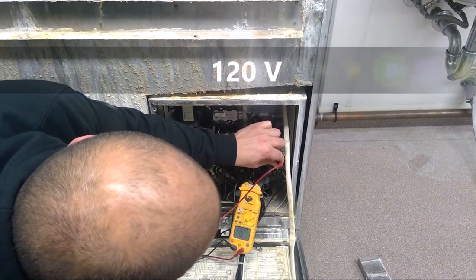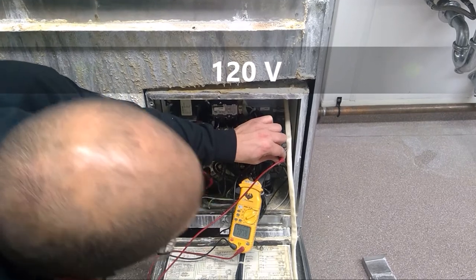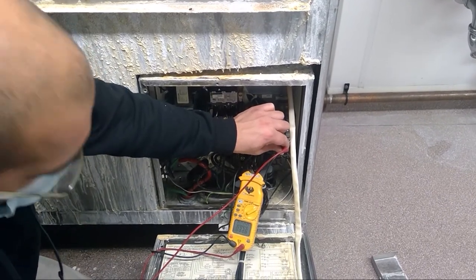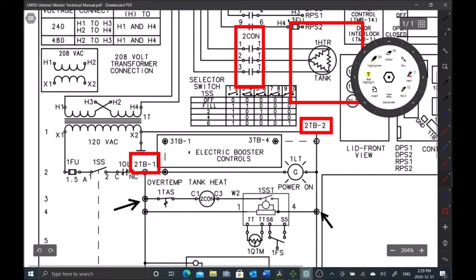I do have 120 volts across that TB1, TB2 terminal block. So we do have power, so that means this whole circuit here is good. We're going to be troubleshooting downstream at this point. We're good all the way to here and across into our transformer on our neutral side. Our power lights on so we know we're good here.